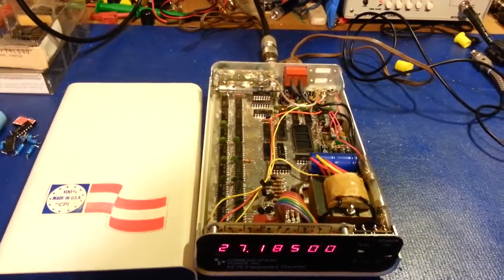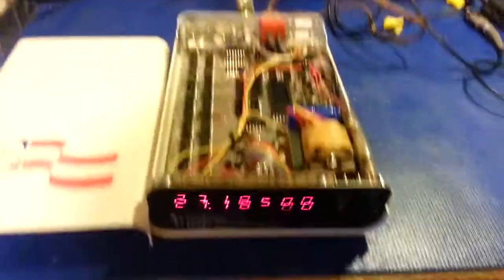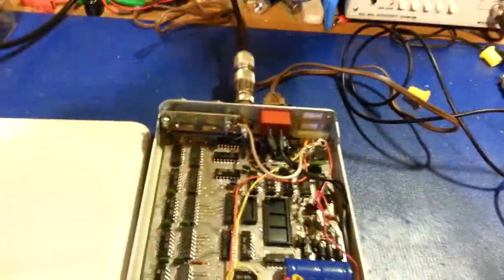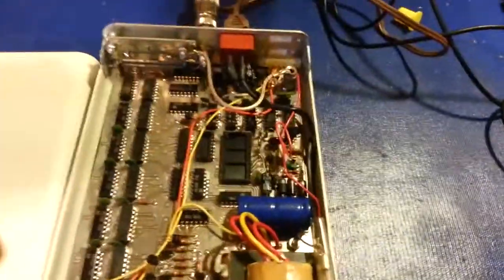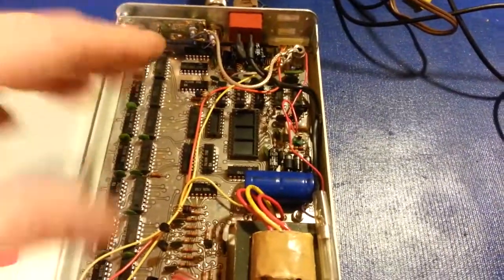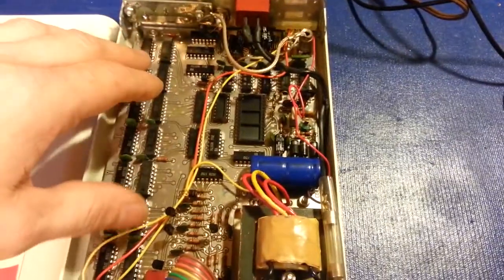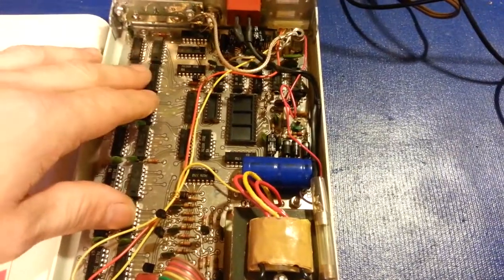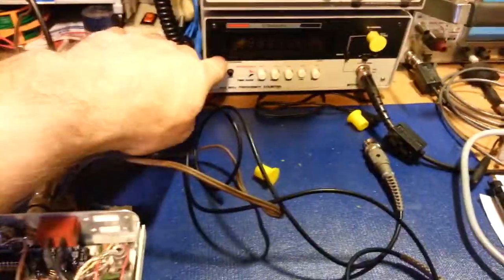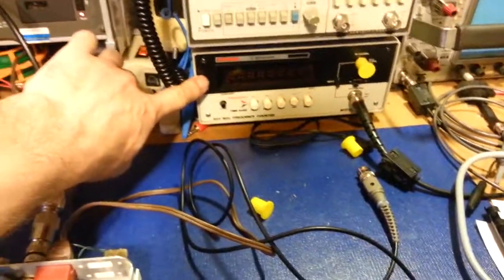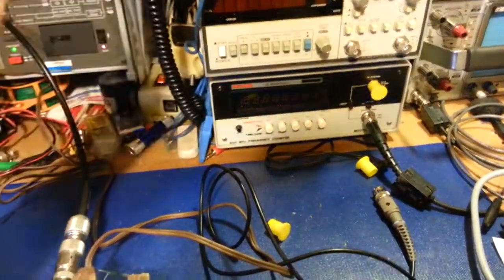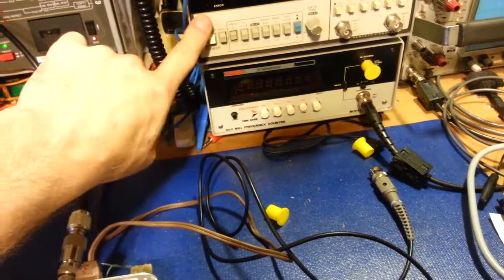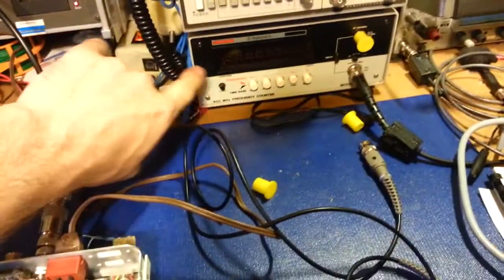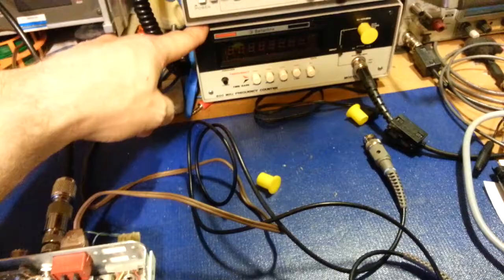Okay, so here we are back with the cover now off of this. We're hooked up straight into the signal source at proper frequency now out of the signal generator, and it's been calibrated. Very simple as far as calibration goes. Basically turn it on. I'd suggest letting one of these stabilize for at least an hour. It's the same thing as this frequency counter. This one, I don't have a problem. I can turn it on, bam, ready to go, as long as it's plugged in, because this one's got a high stability crystal oven in it. But this one needs to be turned on.